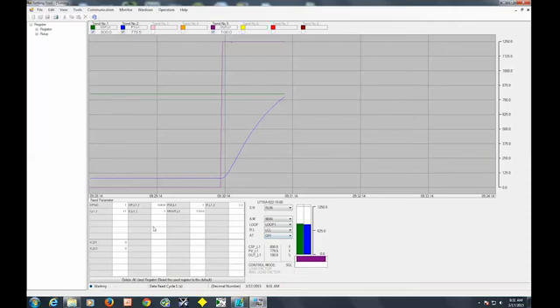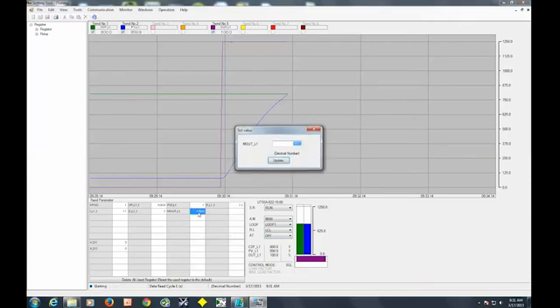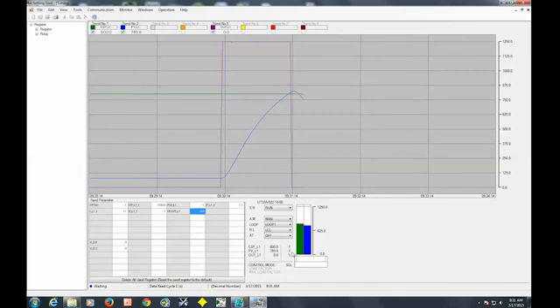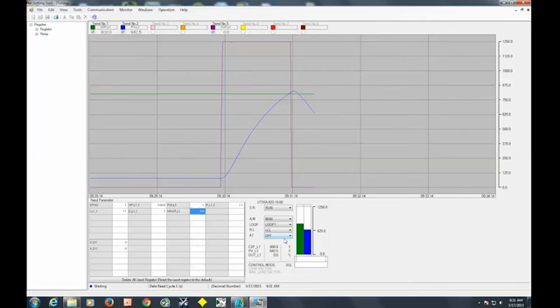So I'm going to actually change our output to 0 so we can start from that point. So right now I've got a set point of 800. My current temperature is around 725, 0 output. The temperature is actually dropping since we don't have an output. So we're going to let that drop a little bit further before we initiate the auto-tune.